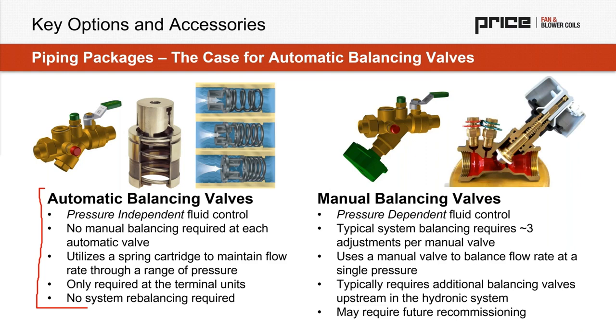And the reality is, it's a few things. First of all, these are pressure independent fluid control orifices. So that means there's no manual balancing required at each automatic valve. It's using a compression spring to maintain flow rate through the range of pressure. And it's only actually required at the terminal. So we can remove more balancing valves upstream on risers or takeoffs or, you know, branches when we use auto versus manual valves. Manual valves are about 30% less expensive. So about 30% less. The reality is the cost and labor associated with system balancing generally outweighs the broader solution and the cost effectiveness of it. So that's kind of my appeal to the group here.